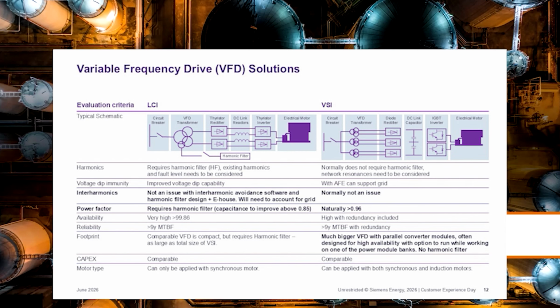So both types are water cooled typically when you get above 10 megawatts, and water cooled drives have their own water cooling loops, but it's another thing that you want to test in your string testing to verify that cooler performance, because these are going to want to get really hot.